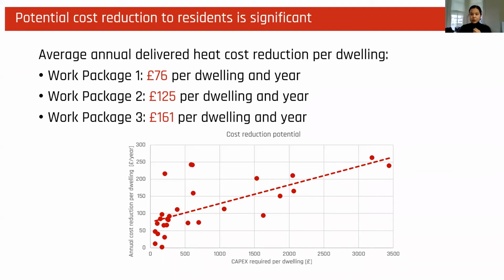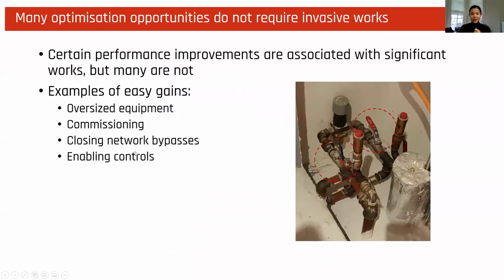And to look at some of the more specific interventions that are low cost but do contribute with easy gains, we can see that in many cases there was oversized equipment, where equipment such as pipework and radiators were found to be oversized, which means essentially that system temperatures can be dropped without needing any more invasive works across the network. And this is an item that will be further developed in detail by my colleague James later on in this session.